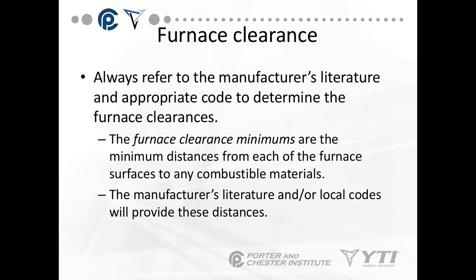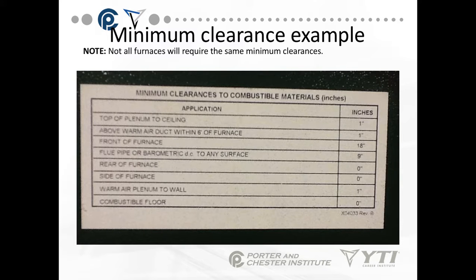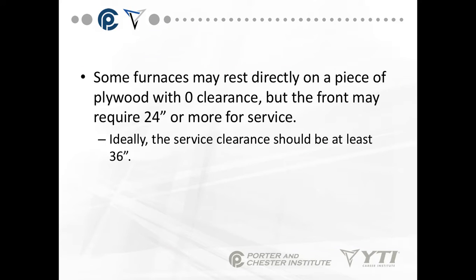For furnace clearances, you'll always want to refer to the manufacturer's literature and appropriate code to determine furnace clearances. Furnace clearance minimums are the minimum distance from each of the furnace surfaces to any combustible material. The manufacturer's literature and/or local codes will provide these distances. Not all furnaces have the same minimum clearances. They're all different. Some furnaces may rest directly on a piece of plywood with zero clearance, but the front may require 24 inches or more for service. Ideally, the service clearance should be at least 36 inches so that a service tech can get in and remove doors and remove components and clean and replace components.